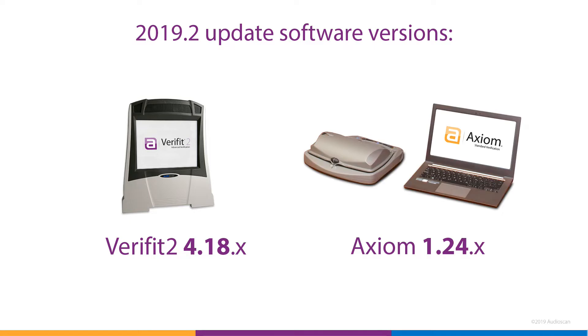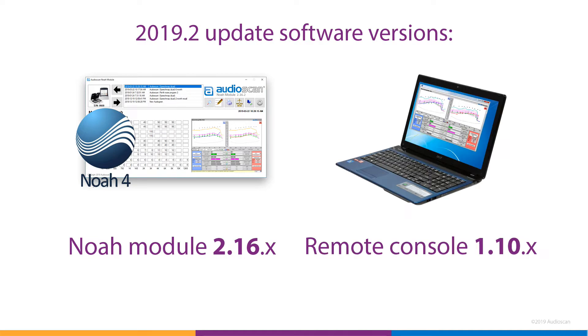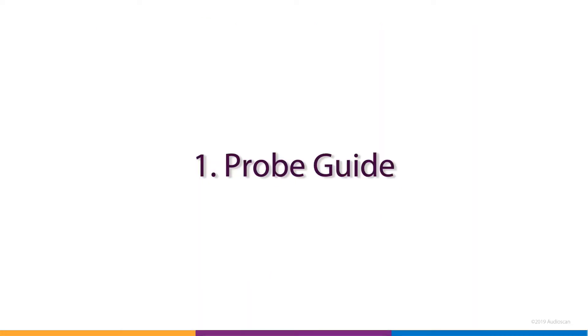The 2019.2 software release includes the following versions: 4.18 for Verifit2, 1.24 for Axiom, 2.16 for the Noah module, and 1.10 for the AudioScan remote console. Downloads for all of these can be found by logging into customer.audioscan.com.